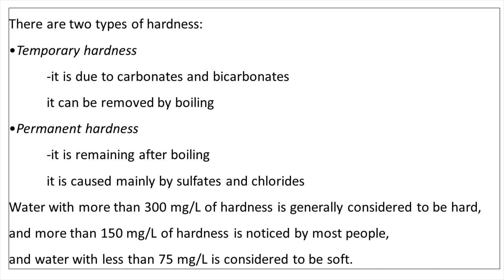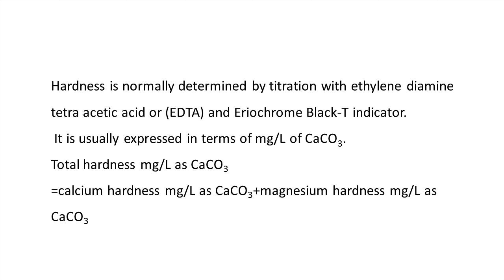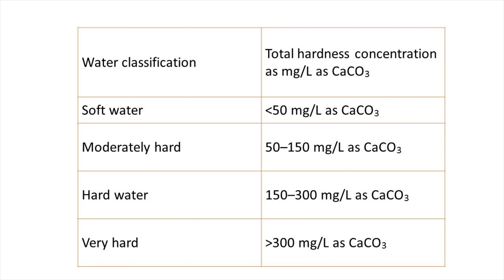Hardness is normally determined by titration with ethylenediaminetetraacetic acid and Eriochrome Black T indicator. It is usually expressed in terms of milligram per liter of calcium carbonate. The total hardness in milligram per liter as calcium carbonate is equal to calcium hardness expressed in milligram per liter as calcium carbonate plus magnesium hardness expressed in milligram per liter as calcium carbonate.